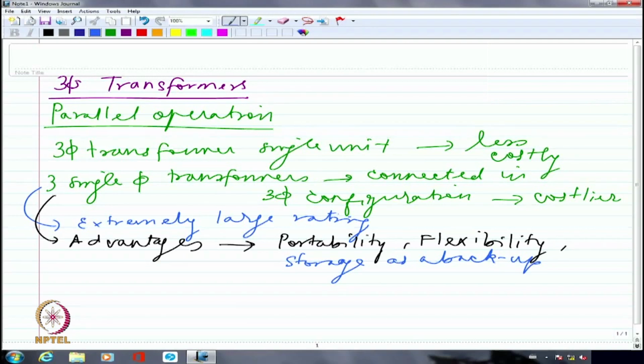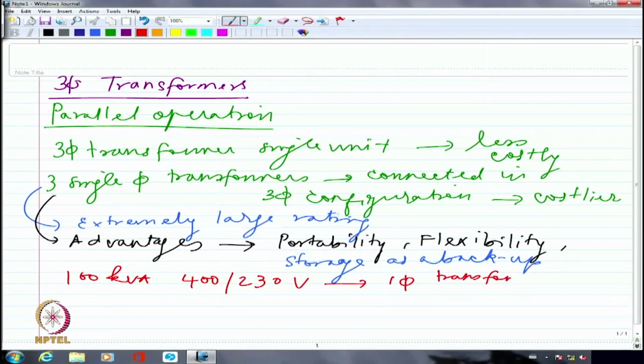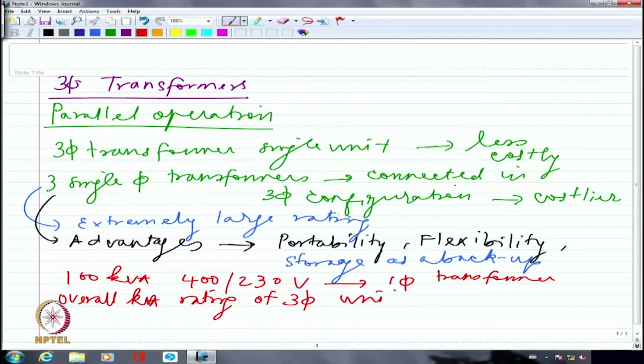transformer bank ultimately. So if I talk about, let us say, a 100 kVA single phase transformer, maybe 400 divided by 230 volts, I'm just arbitrarily taking. So this is a single phase transformer. Then if I am connecting all these three in three phase configuration, the overall kVA rating of the three phase bank will be 300 kVA, because it is 3 times whatever is the single phase unit. Directly you can multiply, because each of them will be able to handle a kVA corresponding to the single phase kVA rating. So I can multiply that by 3 and say that is my three phase rating.